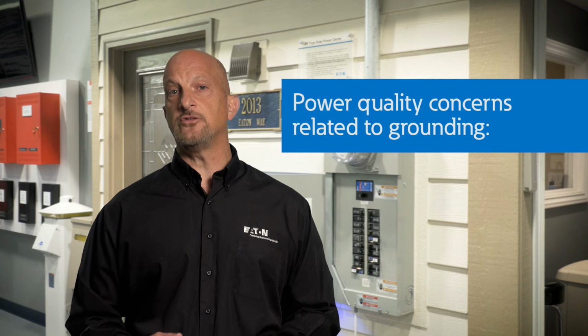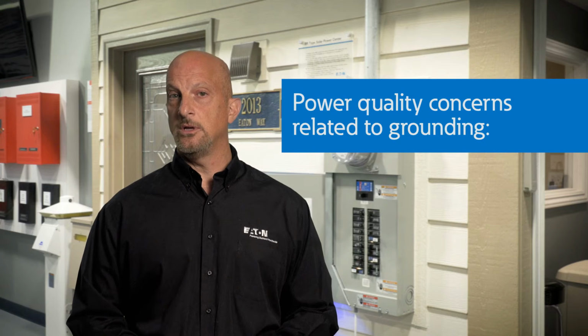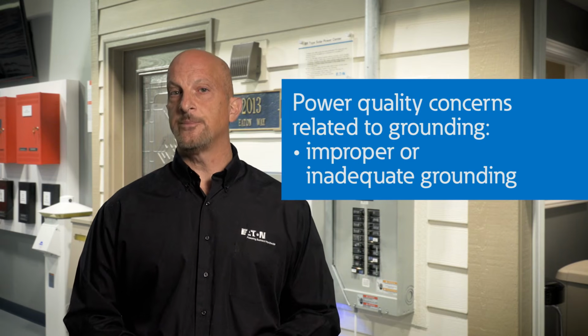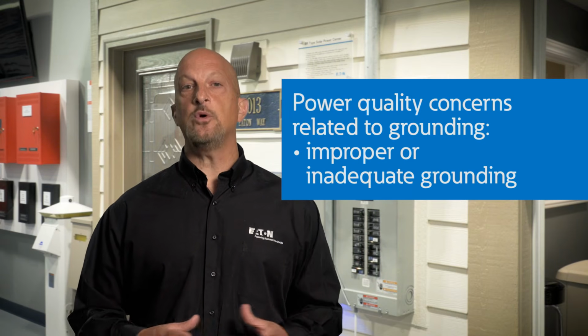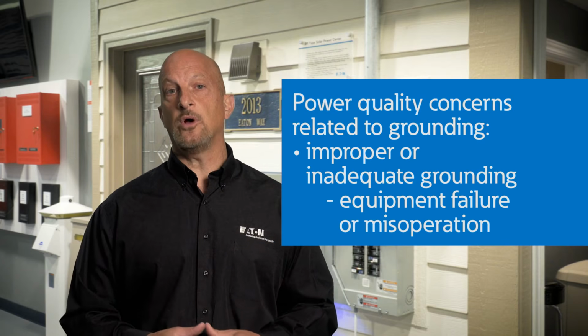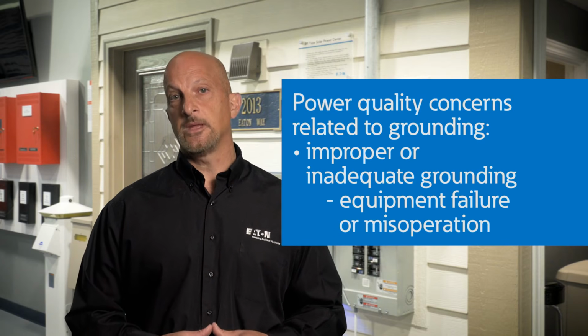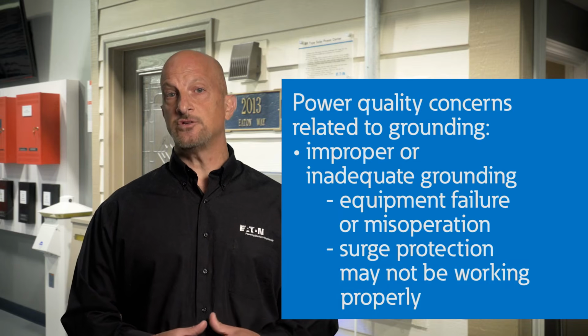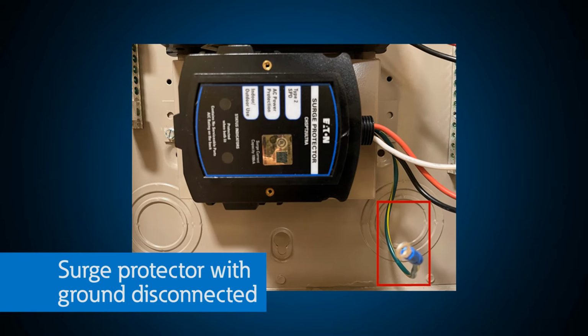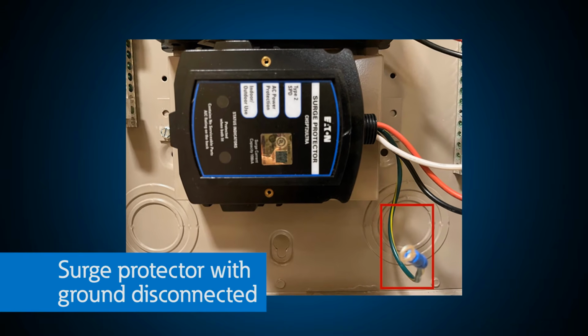Power quality considerations are important as you consider when, where, how, and why to ground your power system. The key is to focus on things that can be controlled and solved. The main power quality concerns that are usually the focus of grounding studies include lack of proper grounding. Beyond the safety concerns, equipment can and will fail with improper or inadequate grounding. In addition, surge protection will be ineffective if it doesn't have a proper path for high-frequency currents.